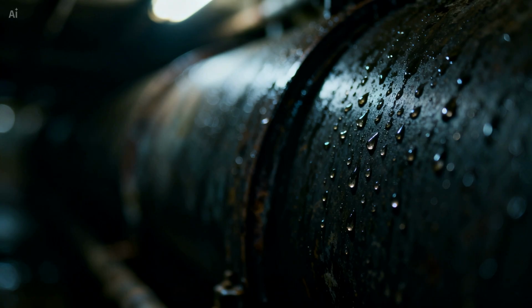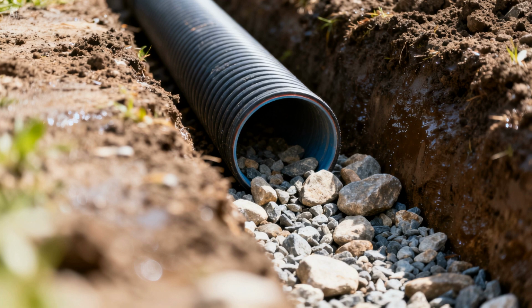In humid climates, earth tubes face a real engineering challenge. When warm, humid air enters a buried pipe and cools below its dew point temperature, moisture condenses on the inside of the pipe. This condensation must be managed through proper pipe slope and drainage to prevent standing water and biological growth inside the tube. In very humid regions like the Gulf Coast, earth tubes require careful design and may need supplemental dehumidification to maintain comfort.